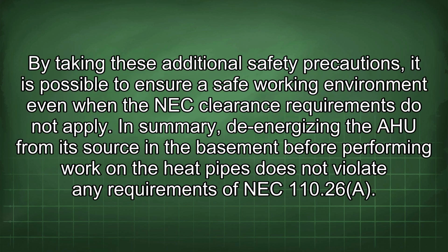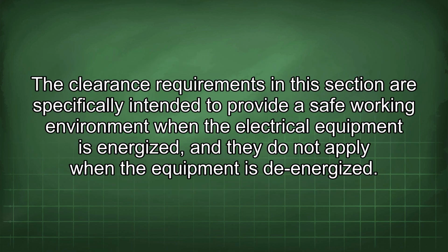By taking these additional safety precautions, it is possible to ensure a safe working environment even when the NEC clearance requirements do not apply. In summary, de-energizing the AHU from its source in the basement before performing work on the heat pipes does not violate any requirements of NEC 110.26a. The clearance requirements in this section are specifically intended to provide a safe working environment when the electrical equipment is energized, and they do not apply when the equipment is de-energized.